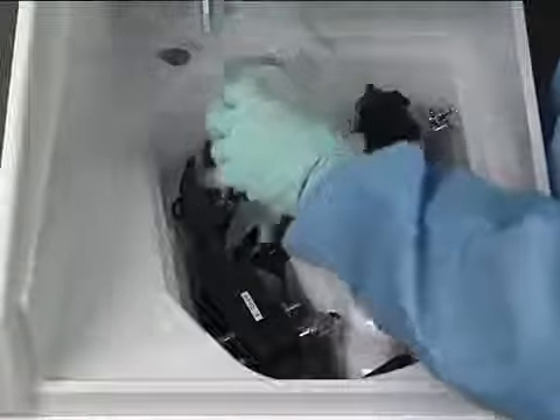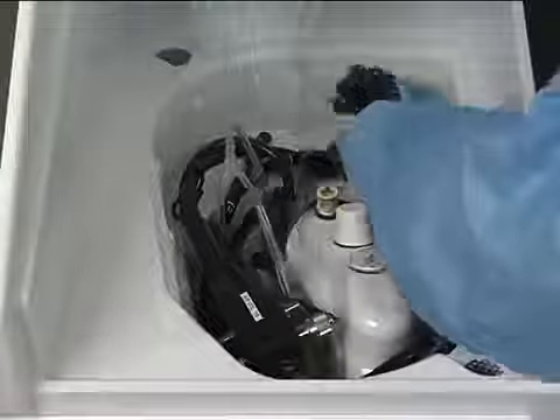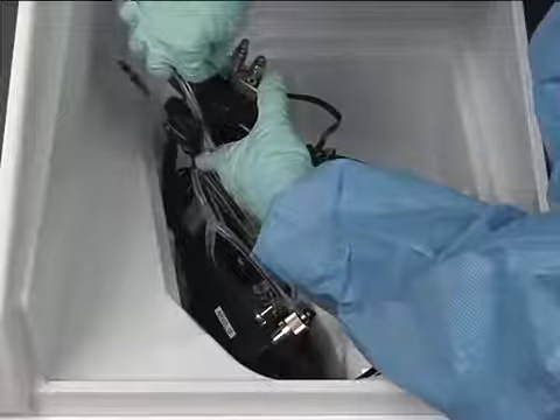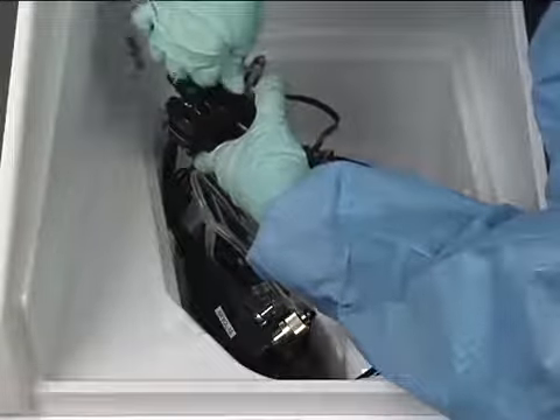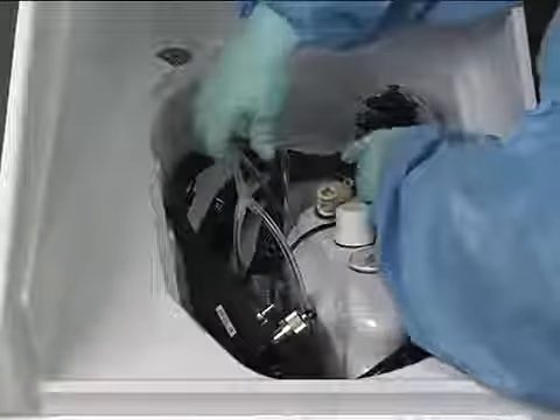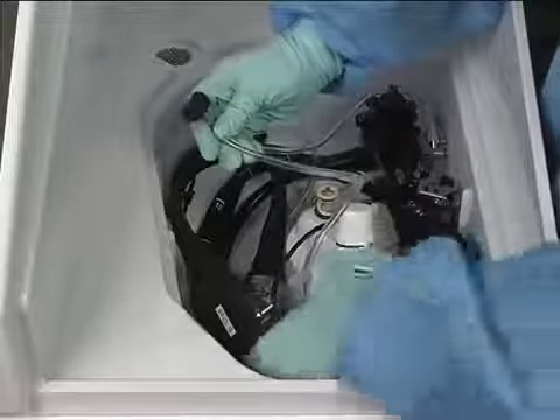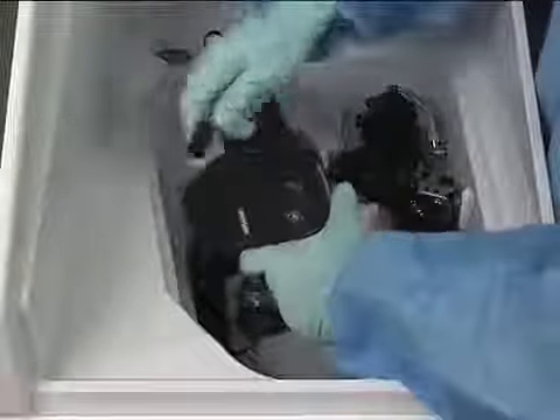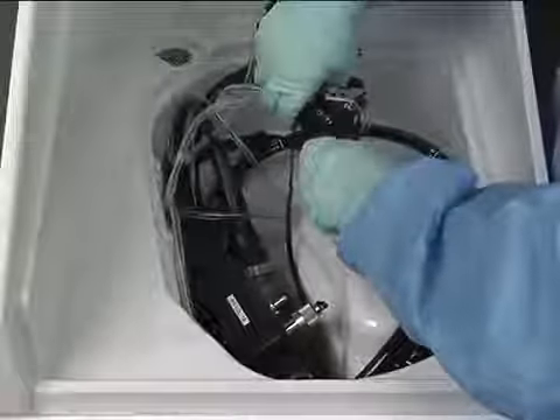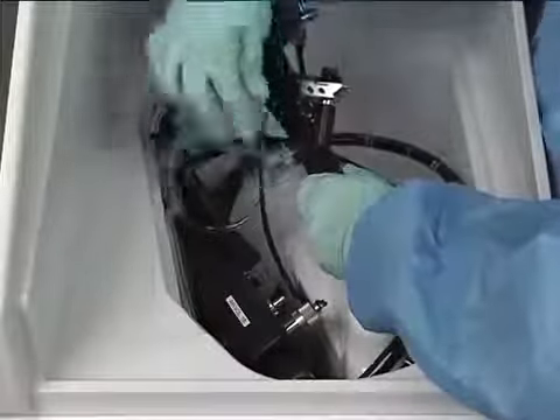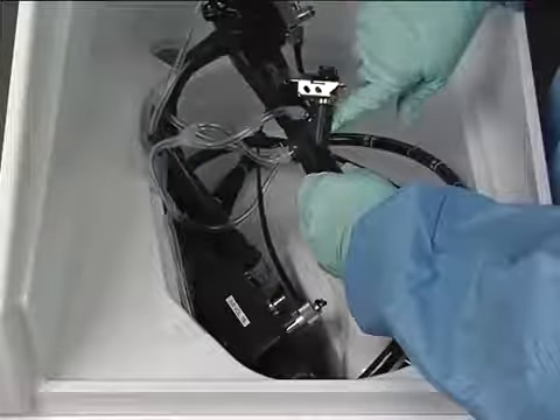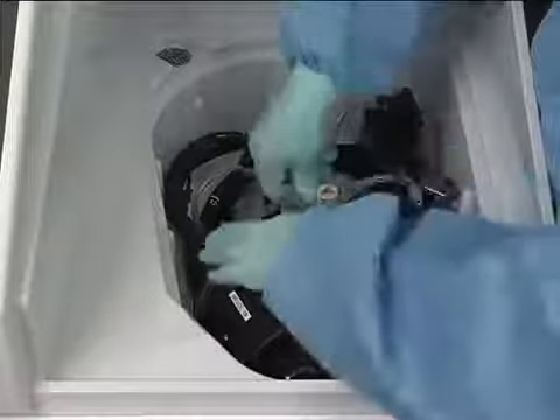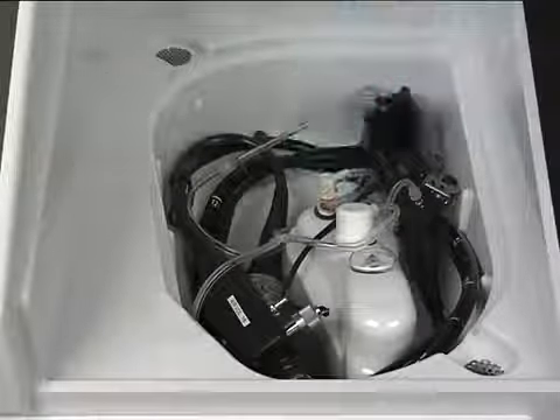Connect two of the luer connectors to the valve adapter. Connect the suction channel tube on the hookup to the suction connector on the endoscope. Connect one of the luer connectors to the water jet luer connector on the scope and the other luer fitting to the lens connector. Attach the inflow end of the basin hookup connector to the basin connector.